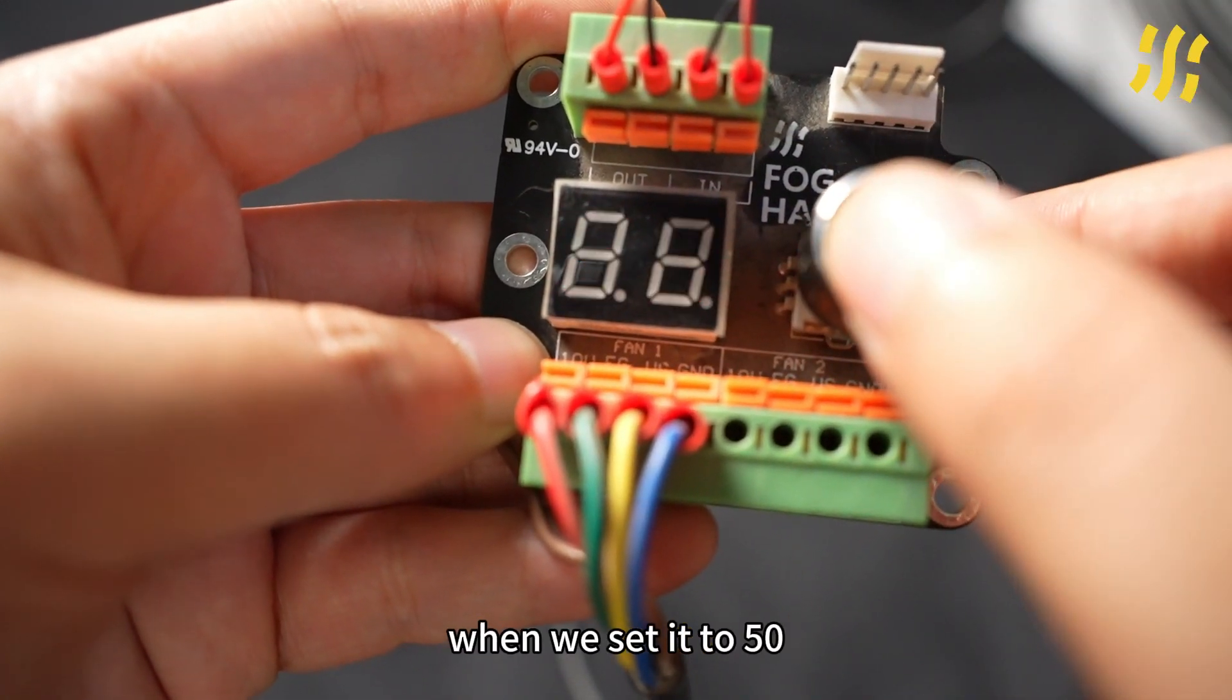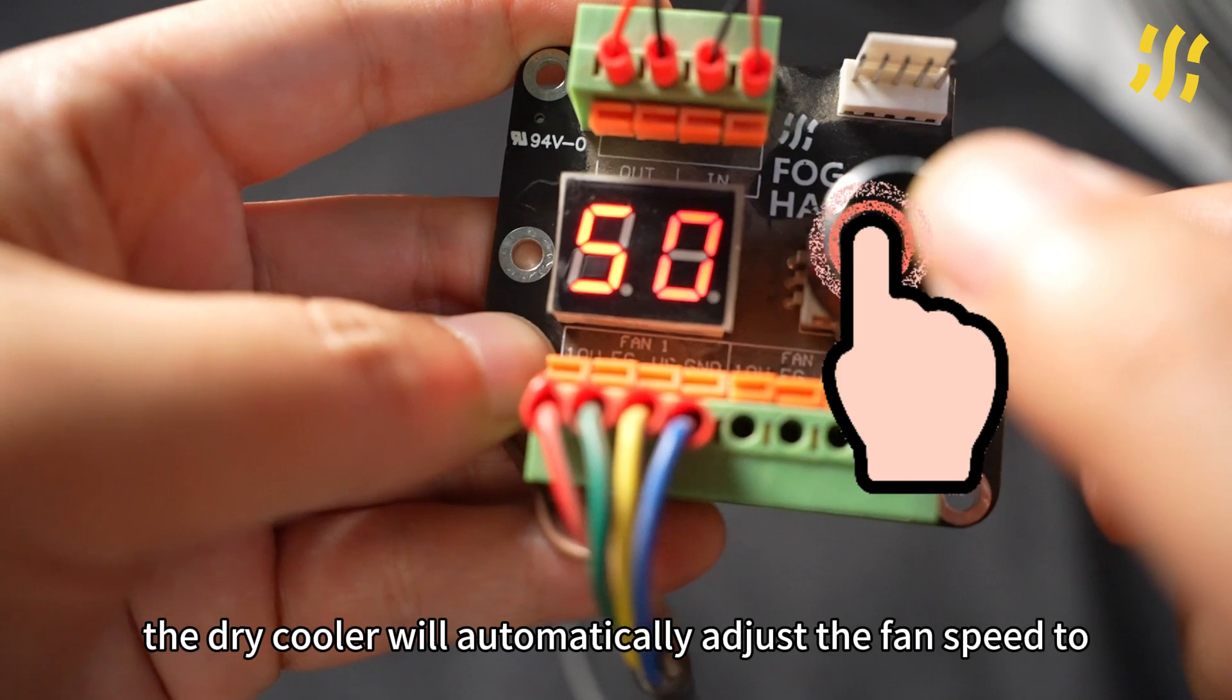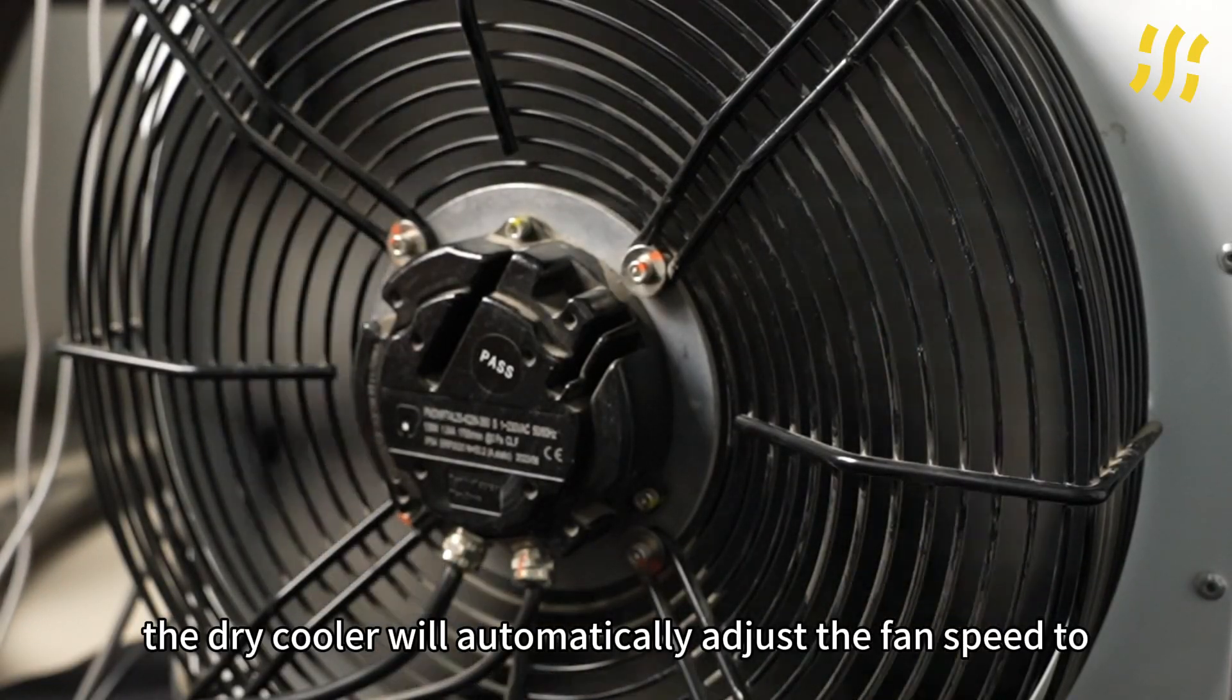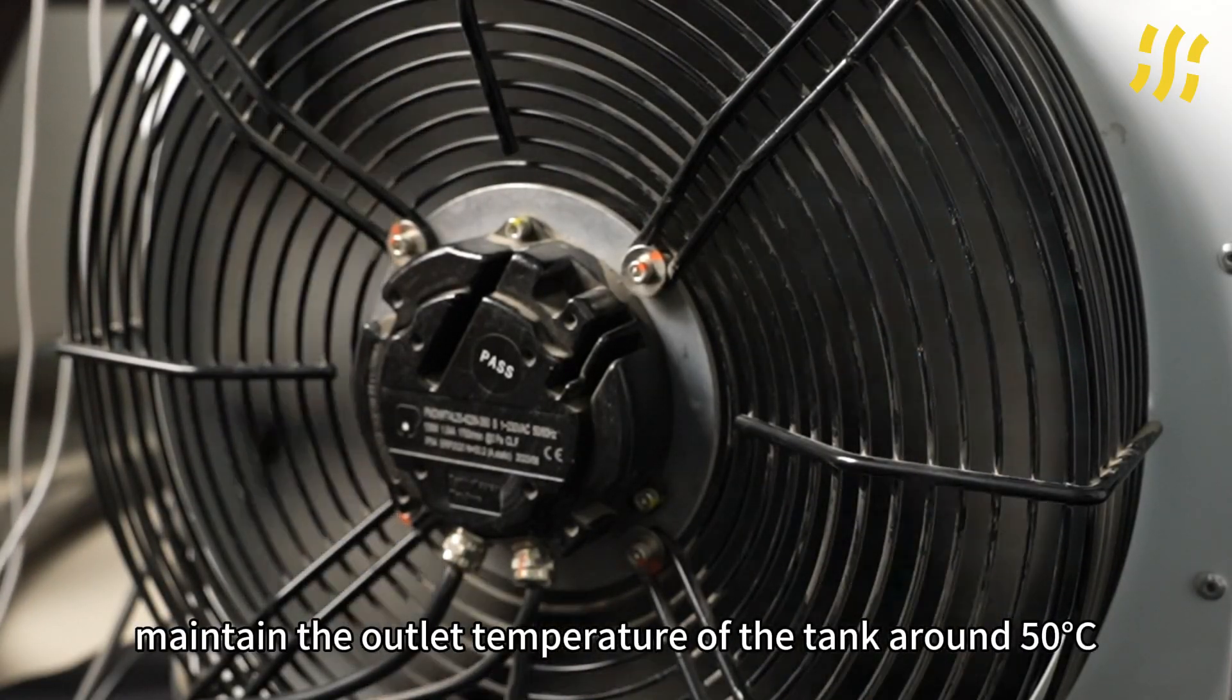For instance, when we set it to 50, the dry cooler will automatically adjust the fan speed to maintain the outlet temperature of the tank around 50 degrees Celsius.